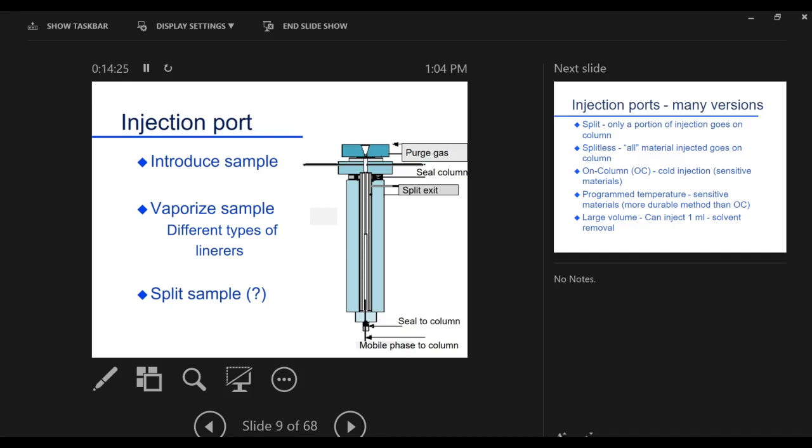So our gas is going to come in here, and some of it's going to go right across, right past this rubber septum. And most of it, though, is going to go down here, down the center of the system. So it will go down the center, and again, some will come next to here. It'll be a little more obvious why these flow patterns and what their significance is. But then here's your analytical column down here.